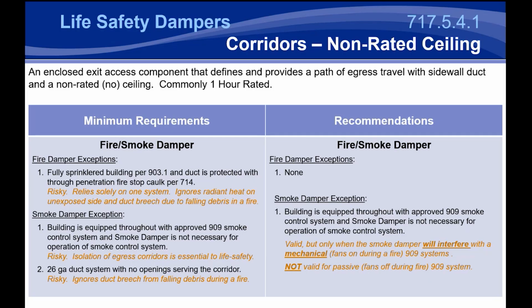So if you just have the fire stop caulk protecting that penetration, there could be the potential for firefighters to dislodge that in larger openings. Because of that, we definitely don't recommend it. There's also the potential for duct breach due to debris. Now, if you've got a building equipped with a 909 smoke control system, it is very unlikely that a smoke damper installed in the corridor will not be connected to that system. So there's really no exception there.